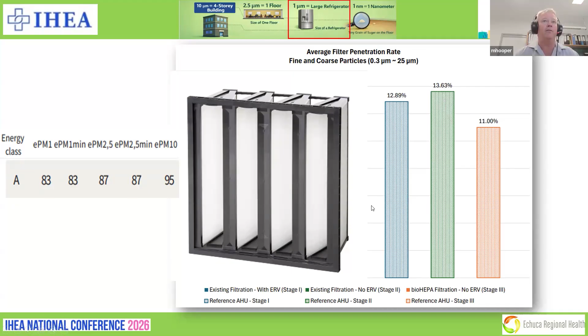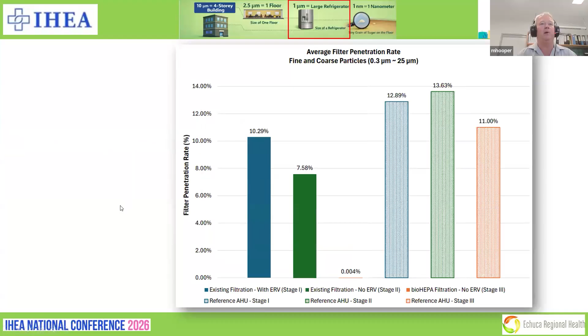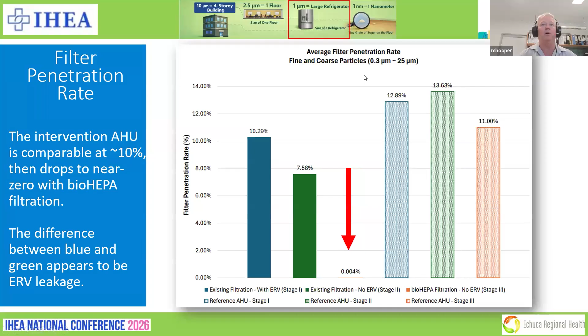So we're pretty happy to know that in real life, the particles we thought our filters were capturing were being captured. When we compare that to our control unit though, for the same study air handling unit with the same concentration of filters, 0.004% of those same particles got through the study unit. So 13% was pretty impressive originally, but getting that down to 0.004 for these particle sizes was a pretty good result.